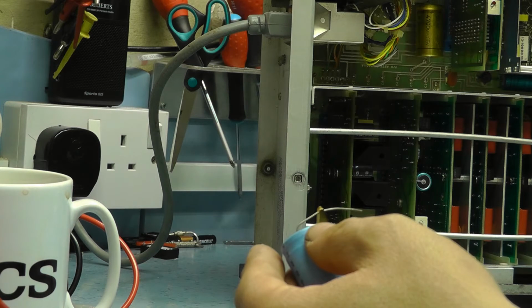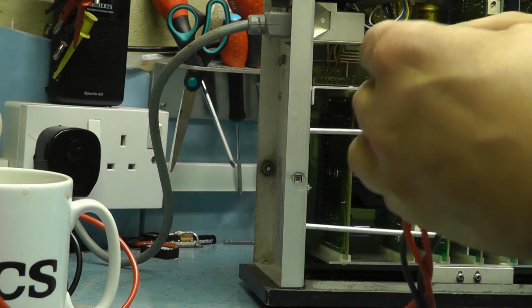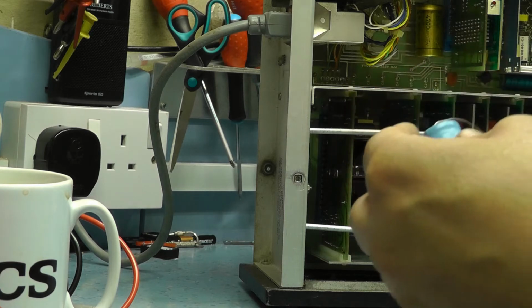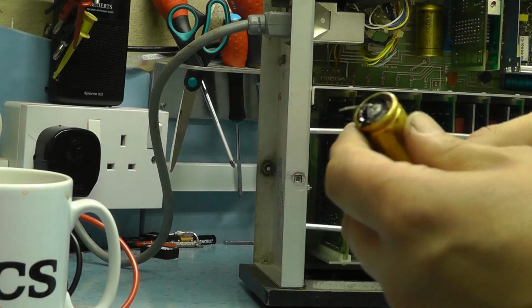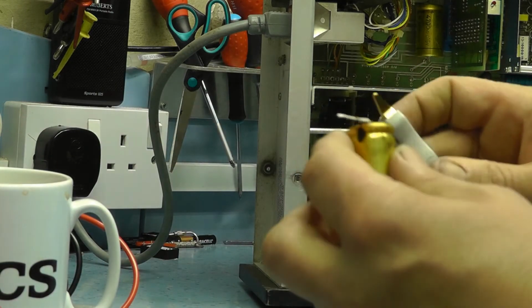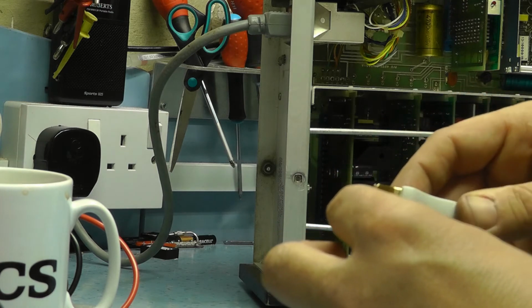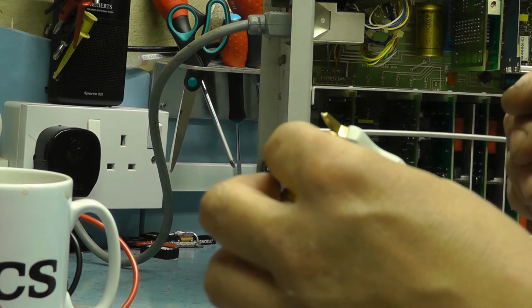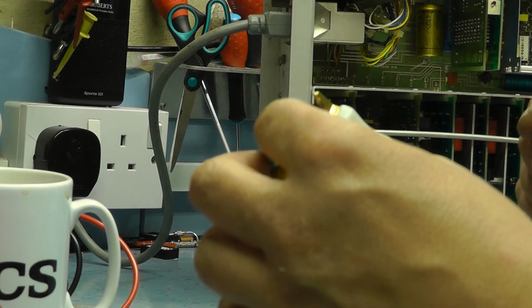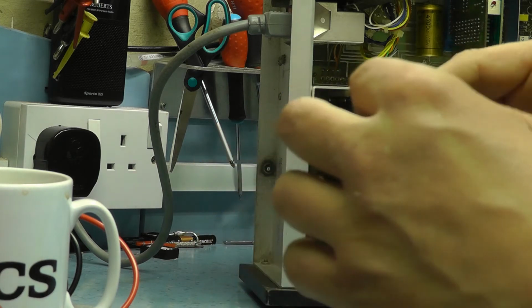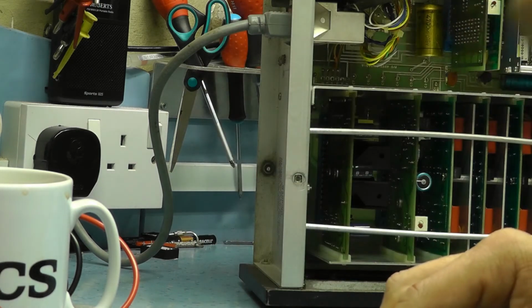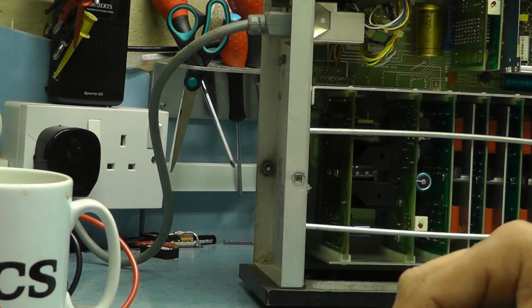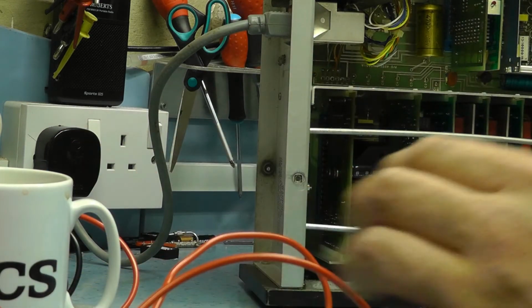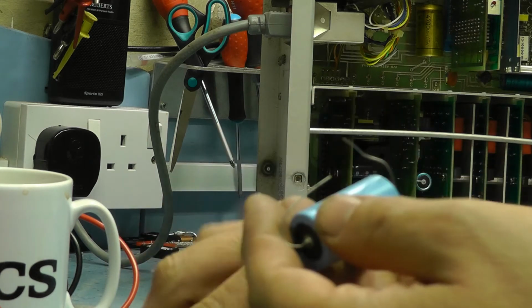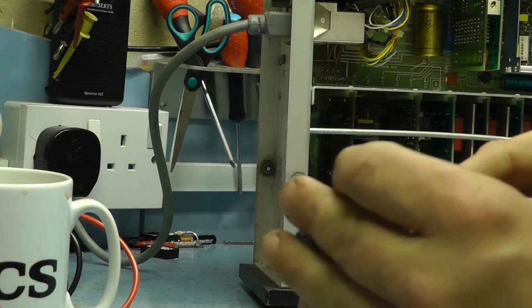And we've come up with 4,400 microfarads - that one measures, as opposed to the one we just took out, which measures 6,800. That's a classic sign actually - if you check a capacitor and it's reading a lot higher than it should, it possibly means the capacitor is actually leaky.